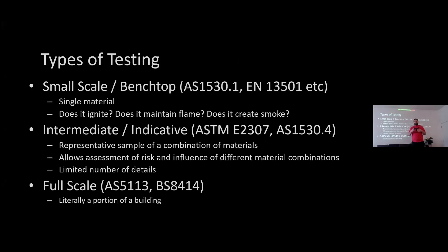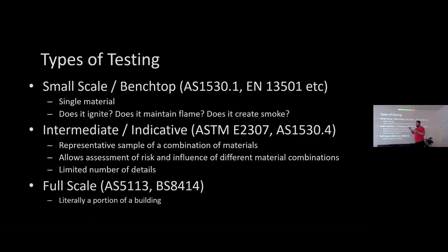Types of testing — there are three different ways to think about this: small scale tests, intermediate, and full scale. A small scale test is: I've got a product or material, I want to know if it's going to be combustible, light it on fire — that's a pretty easy test. Internationally there are five or six different machines you can use; they'll all give pretty similar results. Intermediate is where you take details or parts of walls, put combinations together, and test how that part of the wall works. Then full scale is where you build an actual building, light it on fire, and see how well it doesn't burn.